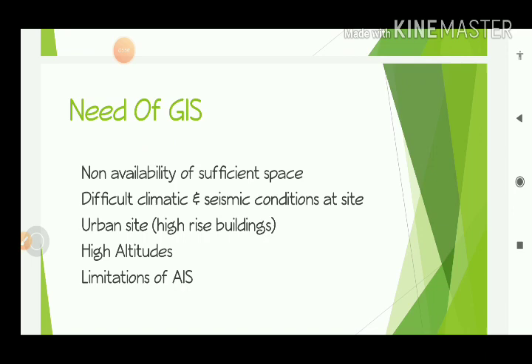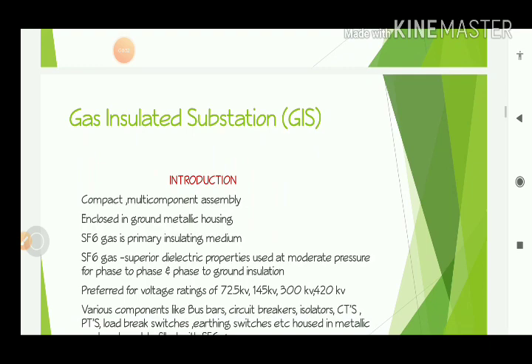All the limitations of AIS should be overcome in GIS — that is why we need the gas insulated substation. GIS is needed when there is non-availability of sufficient space, difficult climatic and seismic conditions at the site, urban sites with big cities and buildings where AIS is not applicable, and high altitudes. All limitations of AIS are overcome by GIS.